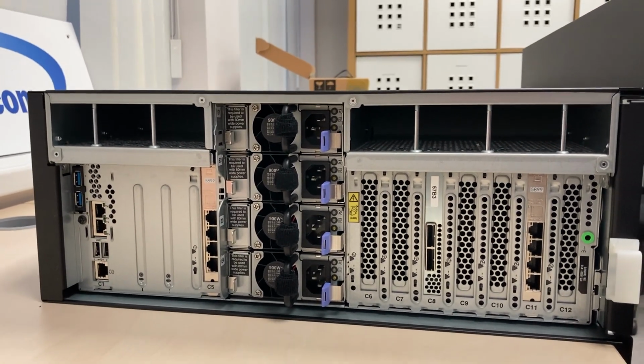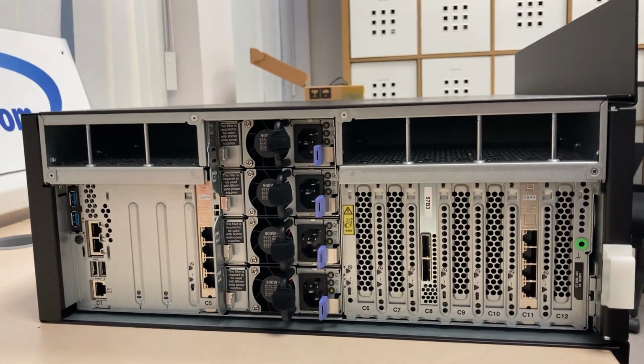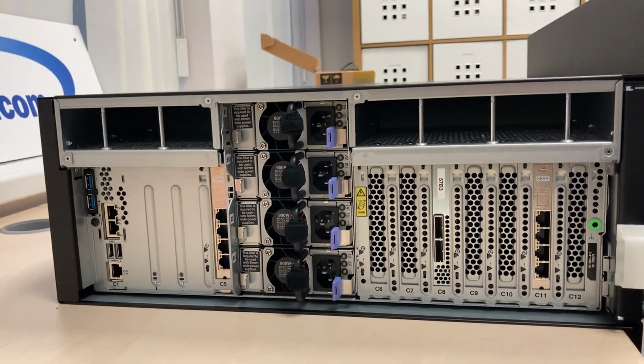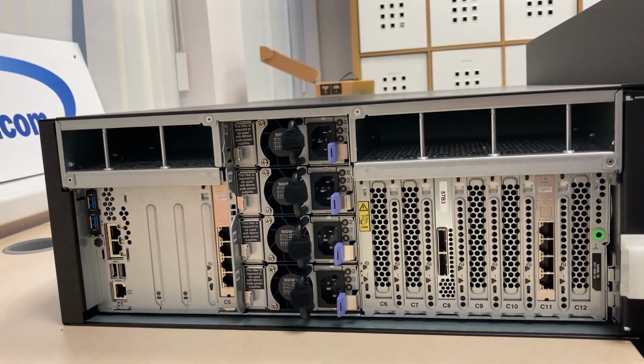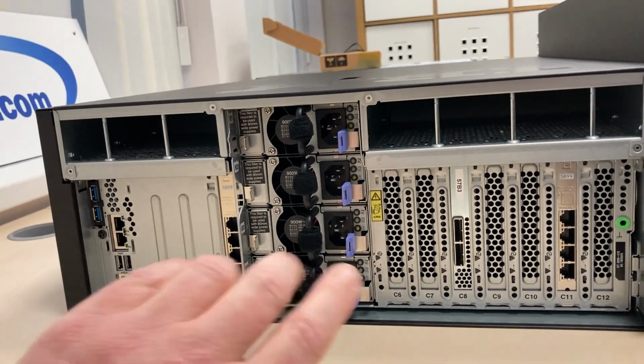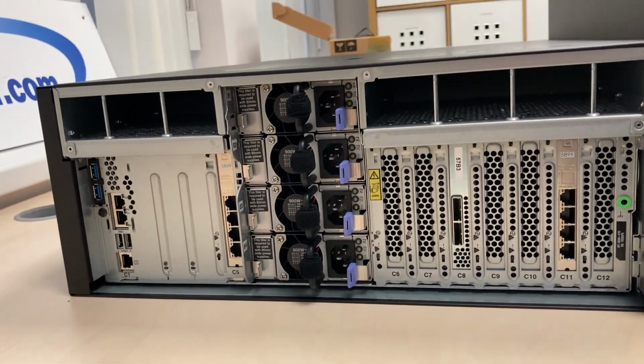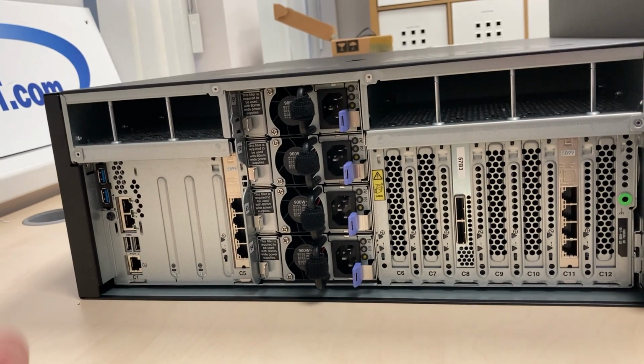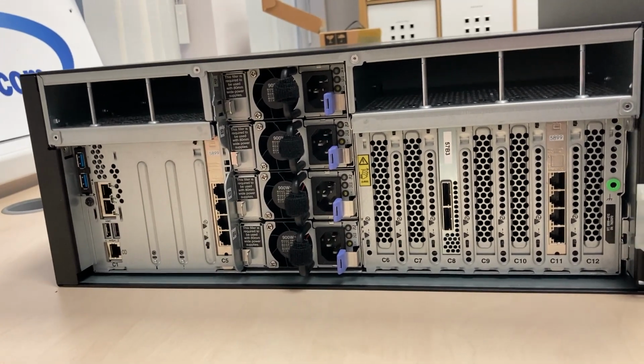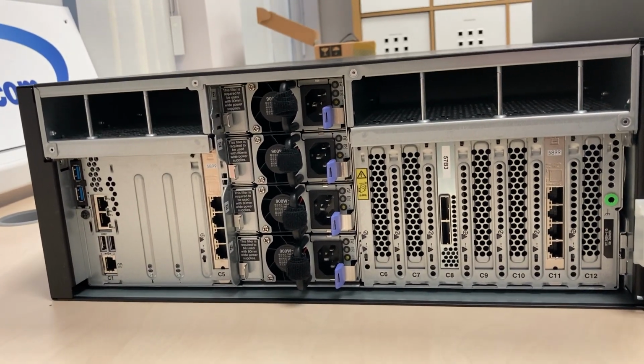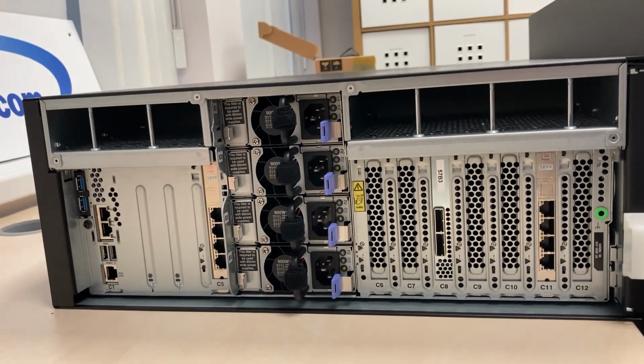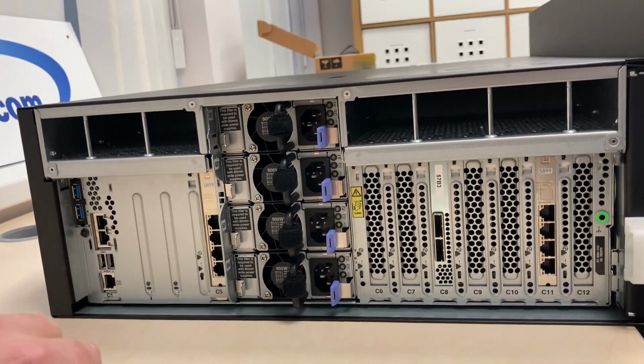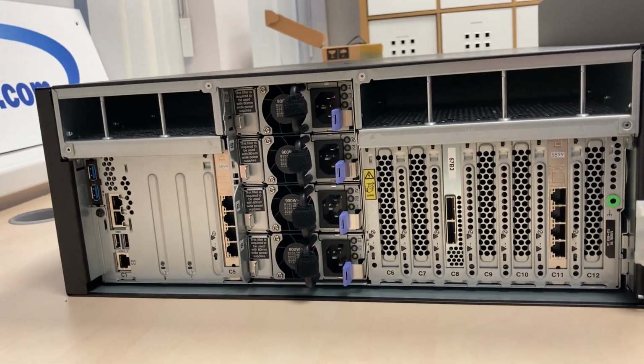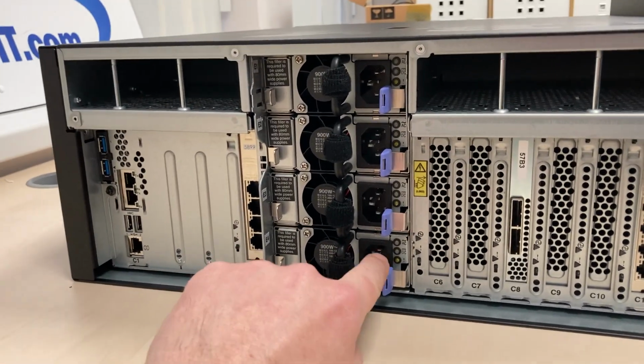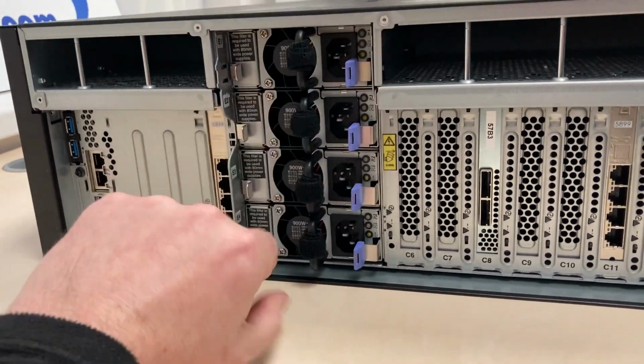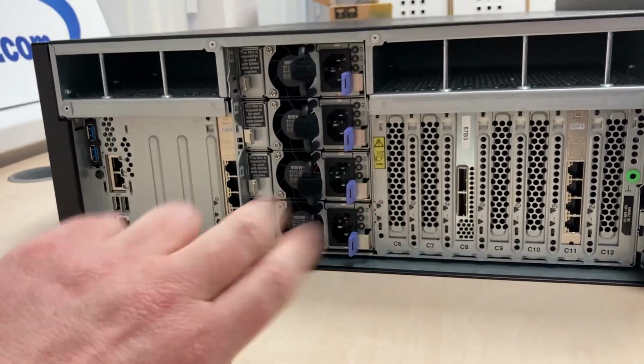On the rack-mounted ones, you tend to find more that there are two power supplies, but it does depend on your geography and your choice. Four power supplies is 4 × 900 watts. You only need two of those four to actually make the machine work. The idea being you have two going from one power source and two from another. So if you're in a data center, maybe two different phases, two different PDUs, maybe two different UPSs, one pair on a UPS and one pair maybe on a utility power supply. Doesn't matter which two, it can be any combination you want to come up with, but there needs to be two.